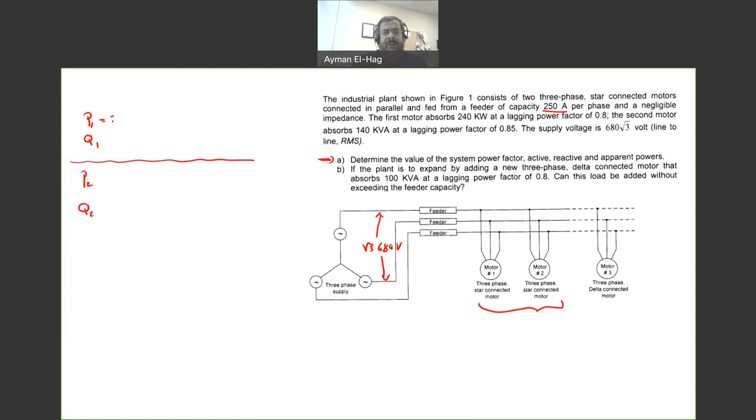So now for load number 1, P1 is already given to us as 240 kilowatt. Now we know the power factor is given to us as 0.8. So theta 1 is equal to cosine inverse of 0.8, which is equal to 36.87.